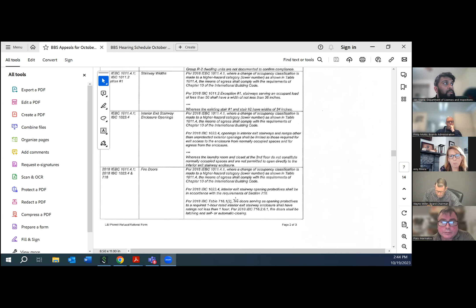And the next one is fire door enclosures. They're required to be one hour rated, but they're definitely not one hour rated. They're definitely not, or they are? They're not, I mean they're not. I didn't see a tag or anything on there. Right, that would be my recommendation, to put fire doors on there to protect the apartments from the hallway, basically.